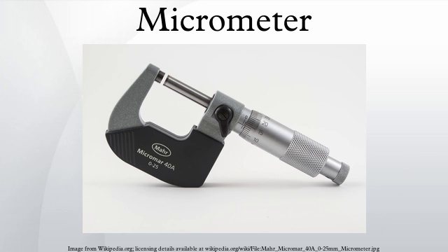Torque repeatability via torque-limiting ratchets or sleeves. A micrometer reading is not accurate if the thimble is over-tightened. A useful feature of many micrometers is the inclusion of a torque-limiting device on the thimble, either a spring-loaded ratchet or a friction sleeve. Without this device, workers may over-tighten the micrometer on the work, causing the mechanical advantage of the screw to squeeze the material or tighten the screw threads, giving an inaccurate measurement. However, with a thimble that will ratchet or friction slip at a certain torque, the micrometer will not continue to advance once sufficient resistance is encountered. This results in greater accuracy and repeatability of measurements, most especially for low-skilled or semi-skilled workers, who may not have developed the light, consistent touch of a skilled user.